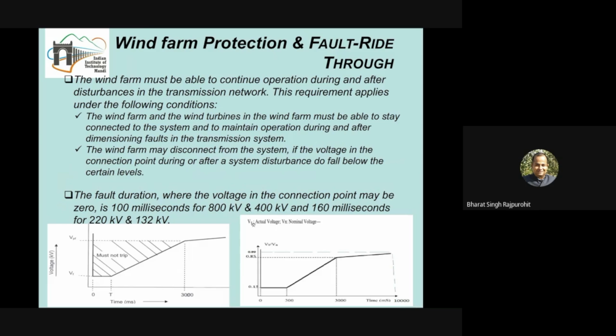So this is the Indian fault ride through. In this case, you just see the left hand side figure. The solid line says that if the voltage level goes beyond this solid black line, that is, if it is lower than this voltage, then the wind farm can be disconnected from the grid. But if the voltage level is up to VF, the wind farm should not get disconnected and must not trip. It should remain connected to the grid and should supply. This timing is from 0 to t seconds.